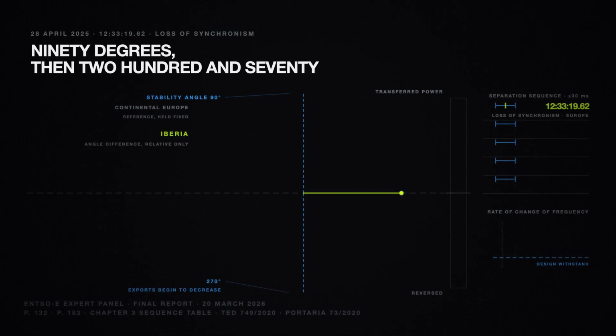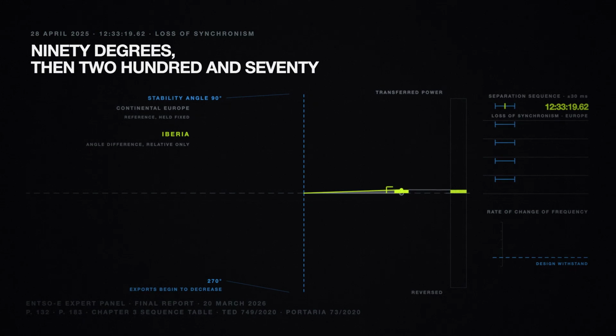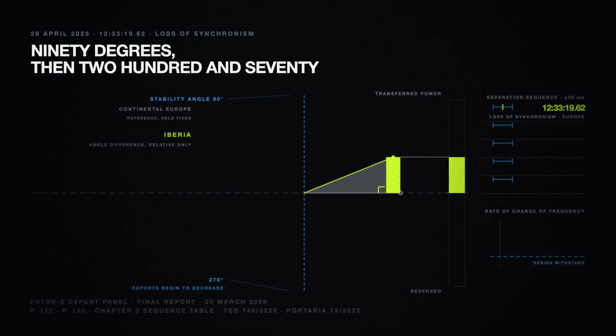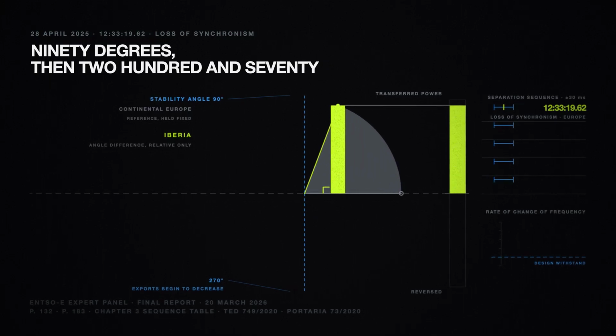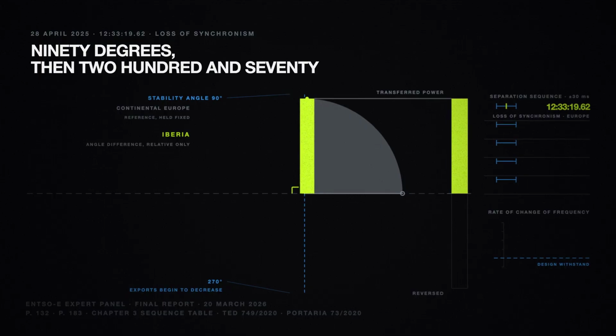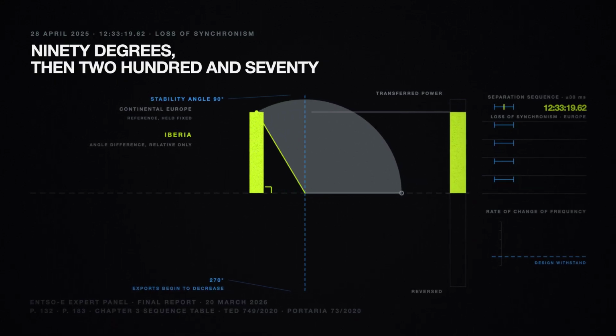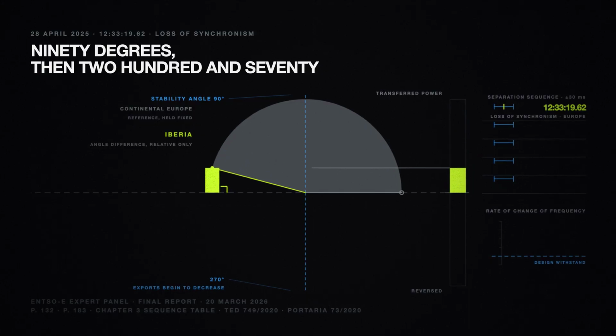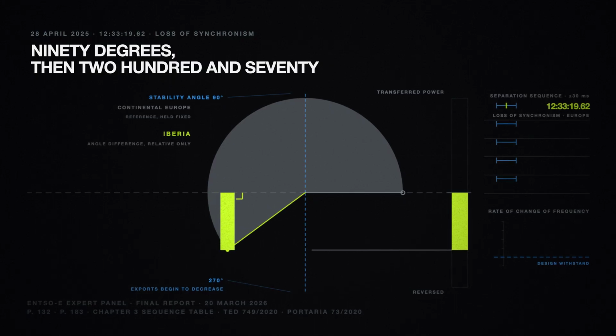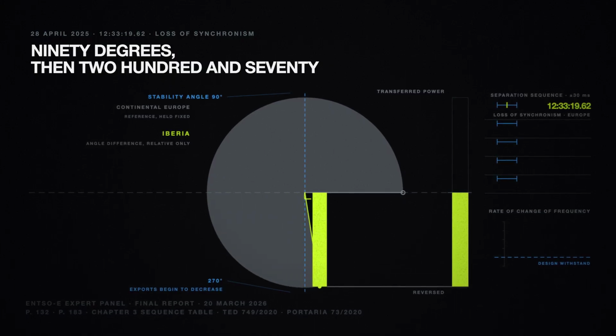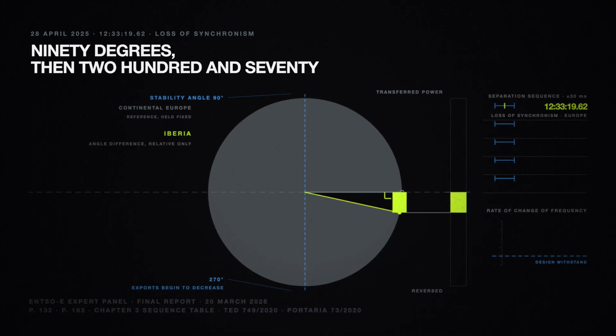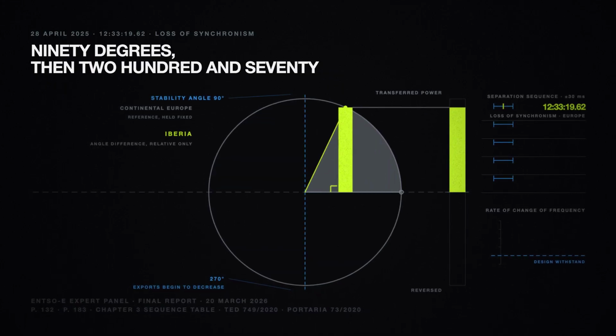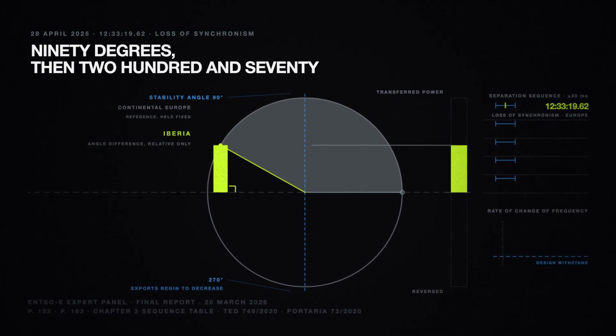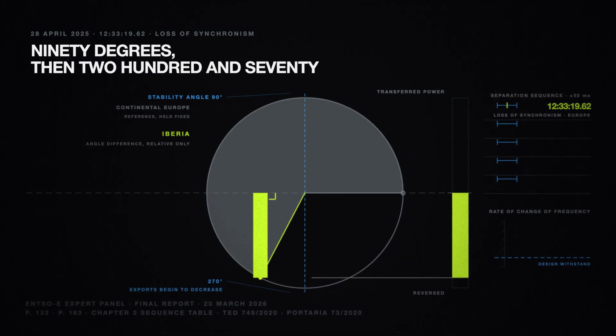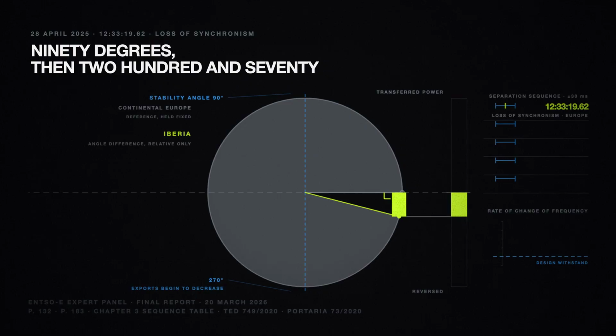12:33 and 19.62 seconds. The Iberian Peninsula stops turning at the same speed as the rest of Europe. The report calls the limit the stability angle and puts it at 90 degrees. It was exceeded. Beyond this angle difference, it writes, any further increase results in a decrease in imported power rather than an increase. When the angle difference reaches 270 degrees, the report continues, power exports from Spain to France begin to decrease. This process continues to repeat with increasing speed due to the growing frequency difference between systems until the systems are fully separated, faster each time round.